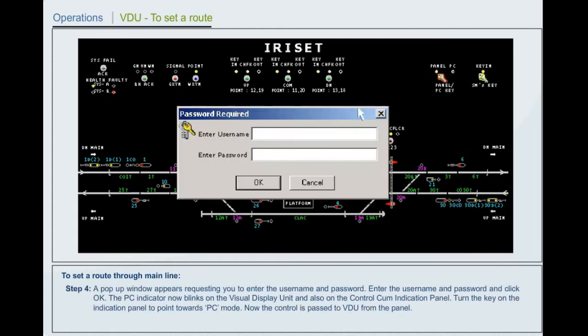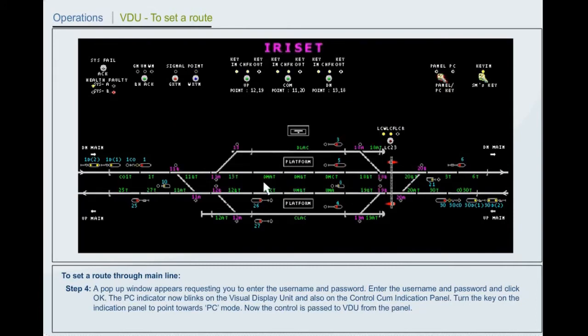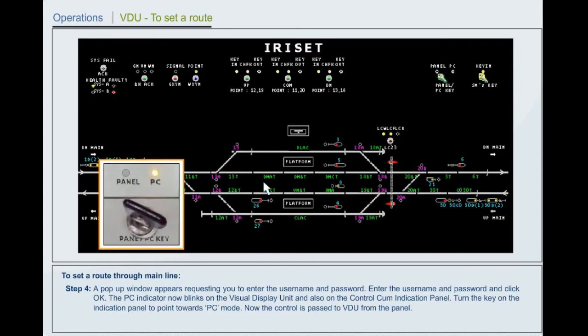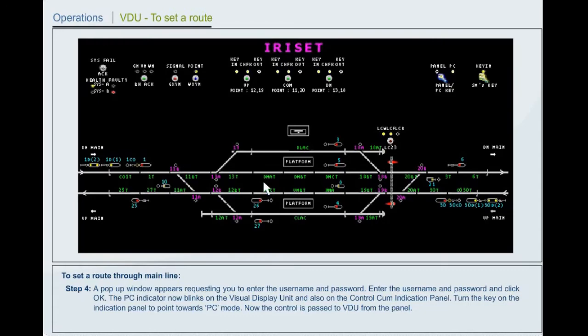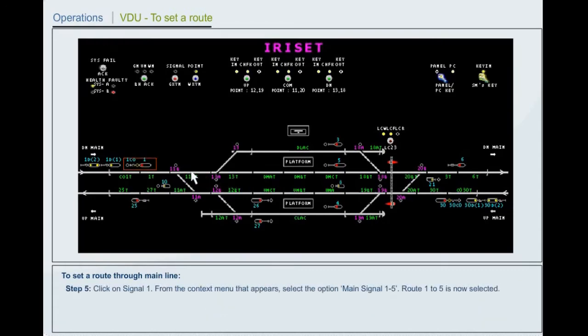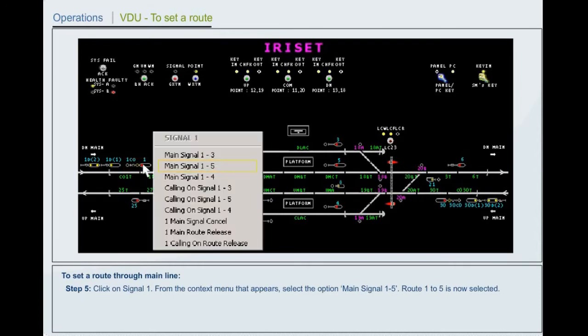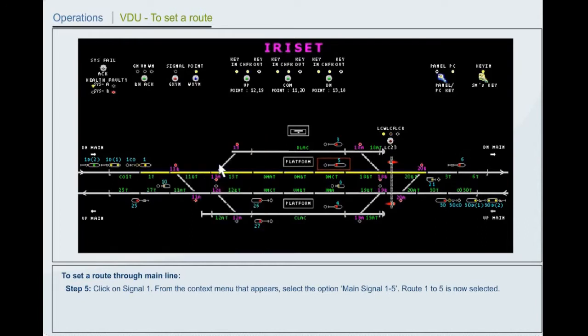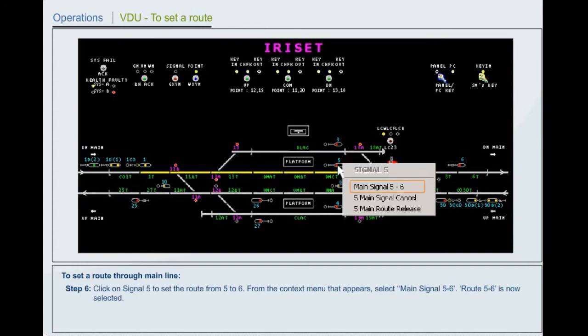Step 4. A pop-up window appears requesting you to enter the username and password. Enter the username and password and click OK. The PC indicator now blinks on the visual display unit and also on the control cum indication panel. Turn the key on the indication panel to point towards PC mode. Now, the control is passed to VDU from the panel. Step 5. Click on Signal 1. From the context menu that appears, select the option Main Signal 1 to 5. Route 1 to 5 is now selected. Step 6. Click on Signal 5 to set the route from 5 to 6.